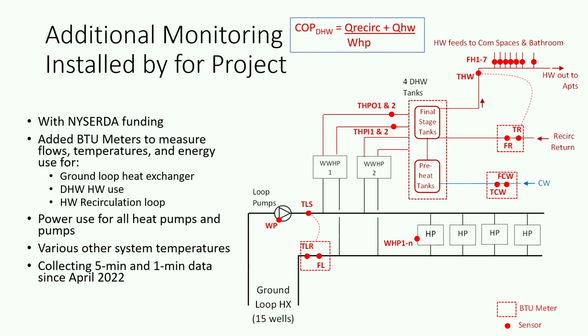And then we also wanted to look into the details of the domestic hot water system. So we measured the energy content, flow and delta T, of the energy delivered to the building, the hot water used by the tenants. And then we also wanted to know what was happening on the recirculation loop. So this is actually one of the first times that I've been involved in a site where we actually measured that, and measured the flow and the impacts on the recirculation loop. And we were able to learn some pretty neat things.